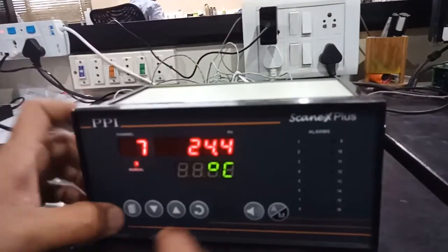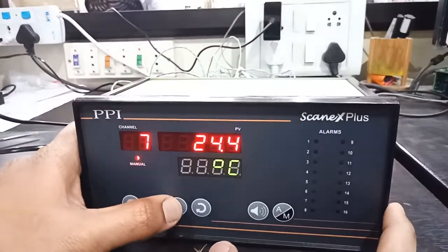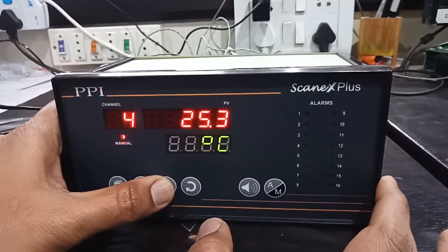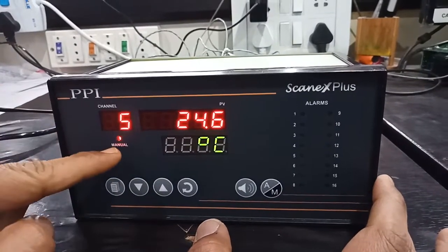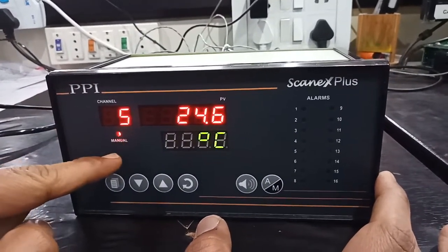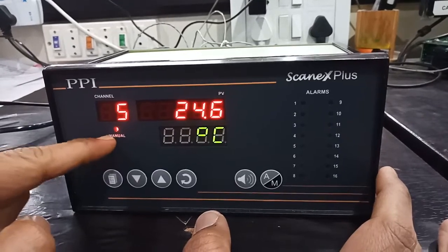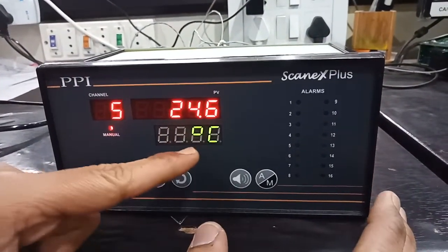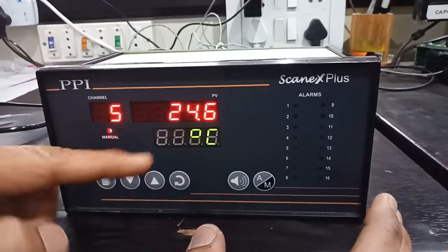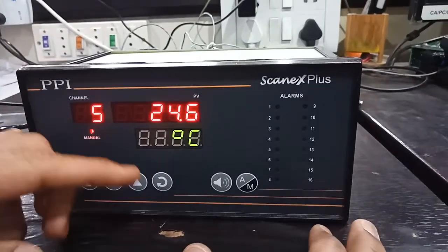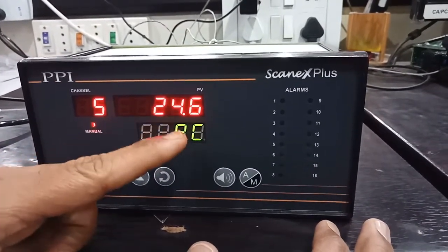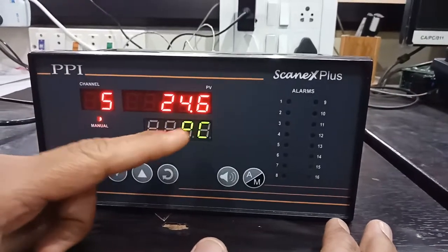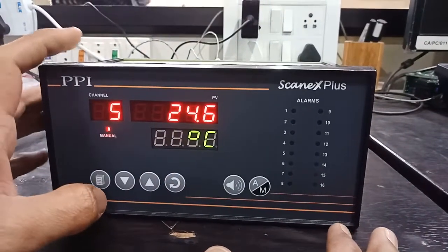If you press the auto-manual key, the PV will be fixed at one particular channel. You can change the values by pressing up and down arrow keys to see the values. Here the manual LED will be on, which indicates it is in manual mode. Below you can see the unit value, degree centigrade, for temperature. You can set the unit of 32 engineering units depending upon the type of input selected.